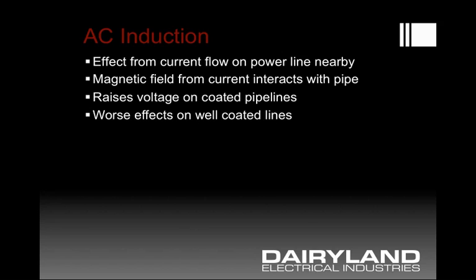Let's turn to the topic of AC induction. This is an effect that occurs where pipelines and power lines are generally in parallel or near each other, and there's an effect from the current flow on the power line. Current flow produces a magnetic field surrounding that current, and that interacts with a steel pipe, raising the voltage on a coated system. If the pipeline were bare, you wouldn't have this effect, but ever-improving insulation systems for pipes have resulted in ever-increasing AC induction as well.